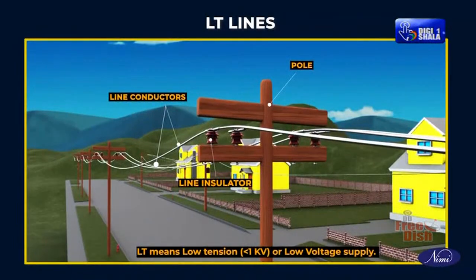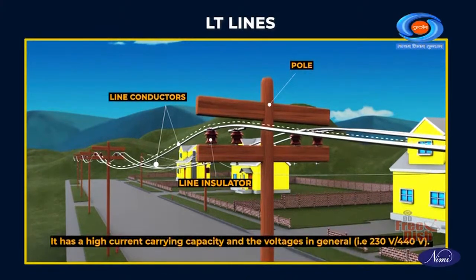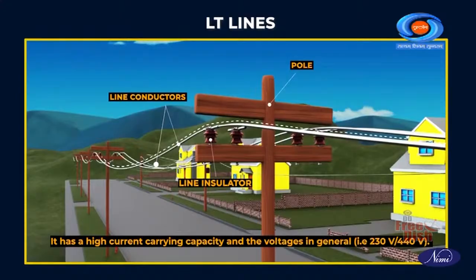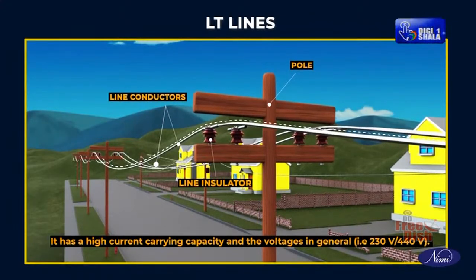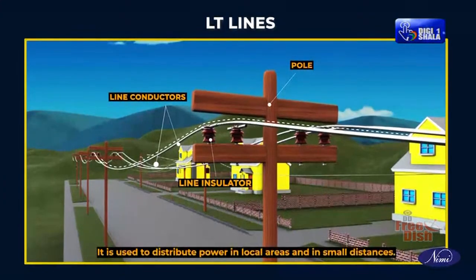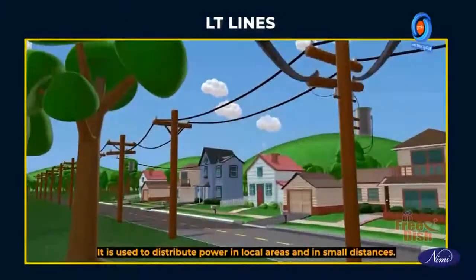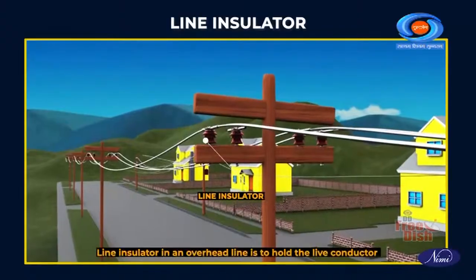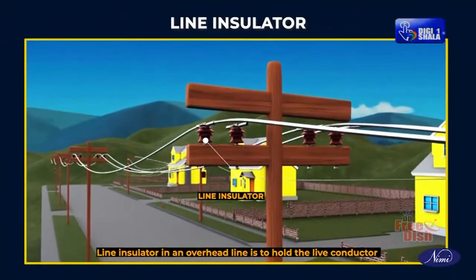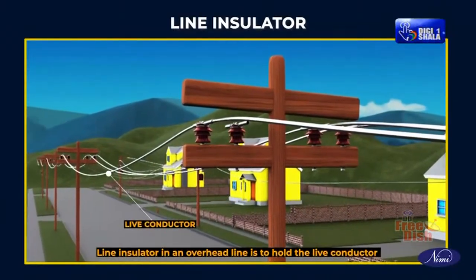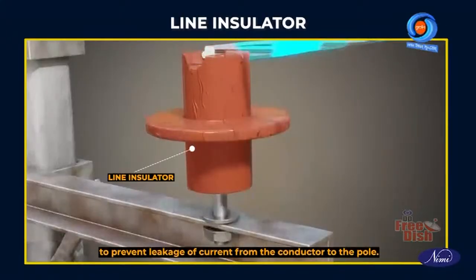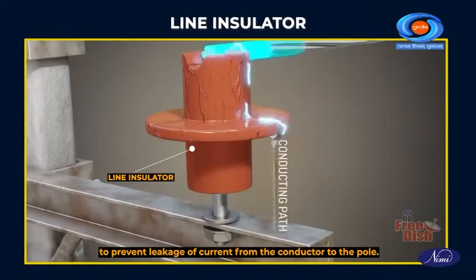LT means low tension or low voltage supply. It has high current carrying capacity and low voltages in general. It is used to distribute power in local areas and in small distances. Line insulator. The line insulator in an overhead line is to hold the live conductor to prevent leakage of current from the conductor to the pole.